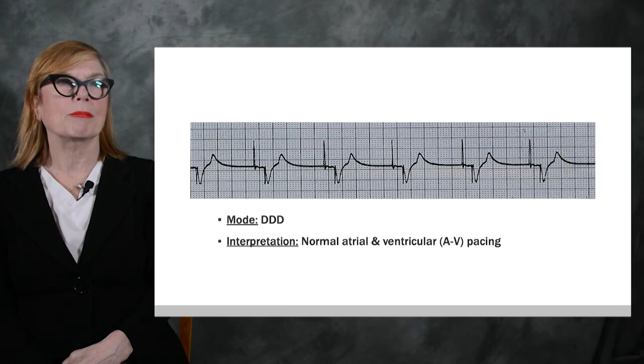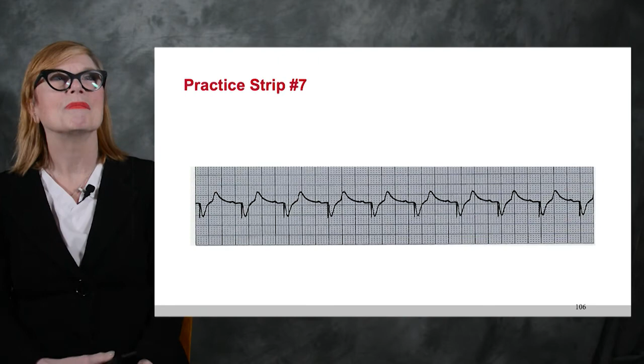You know you've got a dual chamber pacemaker, and you're going to assume that it's dual chamber pace, dual chamber sense, and dual chamber activation. But it's all beautiful because it's normal. So A spike, V spike, and a perfectly appropriate AV interval, DDD. Dual chamber paced, dual chamber sensed, and dual chamber function. And again, I'm going to validate that by looking at what's been set on my pacemaker.